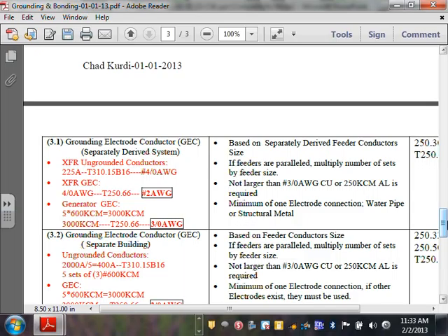And does that sound familiar to you guys, number two? Number two. So your grounding electrode conductor at the transformer, your equipment bonding jumper on the load side at the transformer, both ends, and your system bonding jumper at the transformer end up the same size. They don't have to, but here they end up the same size. Remember, 250, the grounding electrode conductor, guys, you don't have to go higher than what? Number 3/0. Because the transformer size is small, all of them end up being the same.